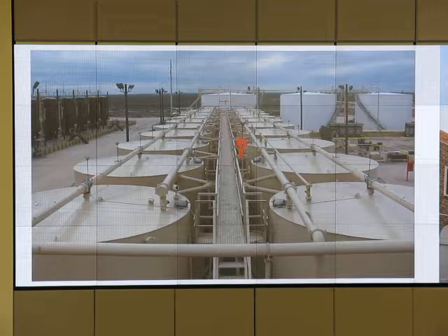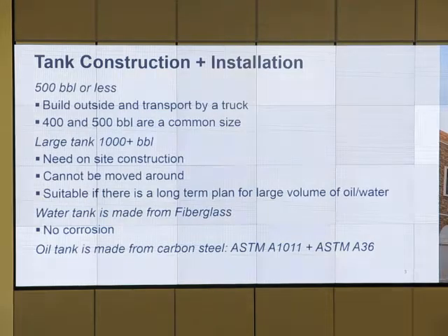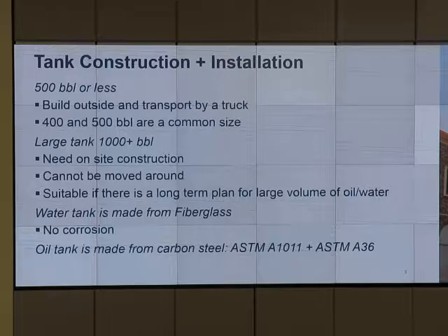And look at the top part. Each line that comes from the top is gas, right? Gas lines connected together, and then it goes to what? VRU. Quad O, right? You remember Quad O? Quad O regulation says you cannot emit more than a certain amount per year. So you have to go to that part and recover those vapors.